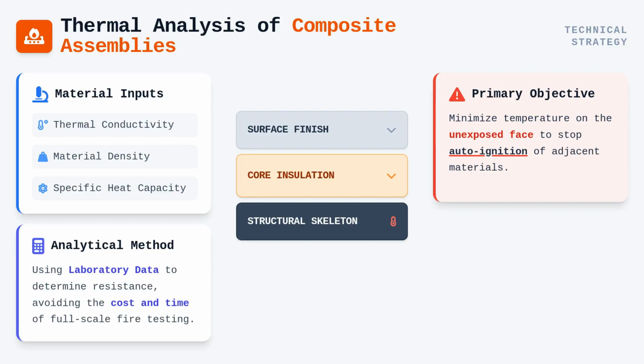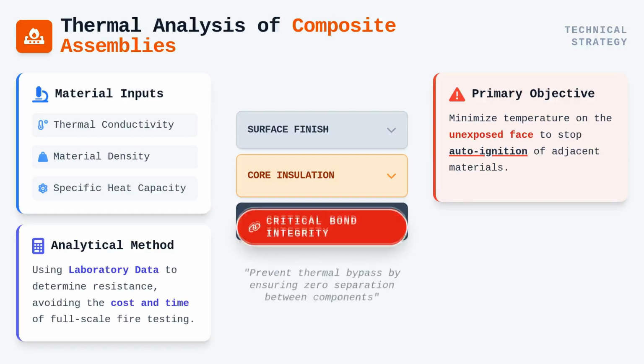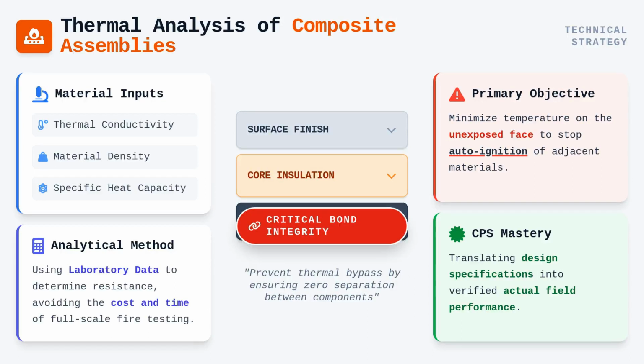We focus on ensuring that the bonds between these materials remain intact, as any separation or failure of the fire-rated barrier allows thermal energy to bypass our protective strategy, potentially compromising the compartments we intended to secure. By mastering these analytical approaches, you gain the ability to verify that design specifications translate into actual field performance, which is an essential skill for any certified fire protection specialist working on sophisticated structural projects.